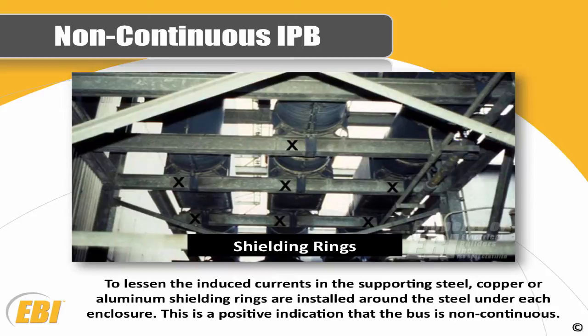This is a picture of a normal non-continuous IPB. One way you can tell that this is non-continuous is the shorting rings that are mounted on the steel, either under or over the isolated phase bus. Those shielding rings absorb all of the induced current. It protects the steel. It keeps the steel from actually absorbing the induced current. Those rings are made out of either aluminum or copper. And this is a positive indication that the bus is non-continuous.